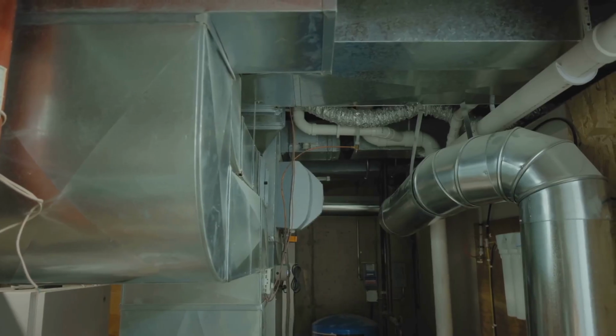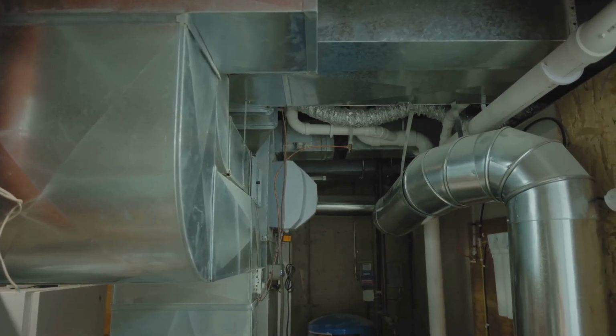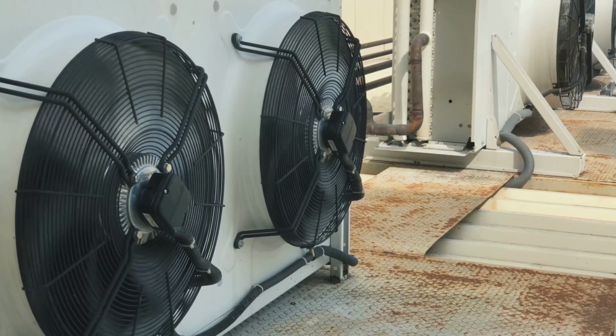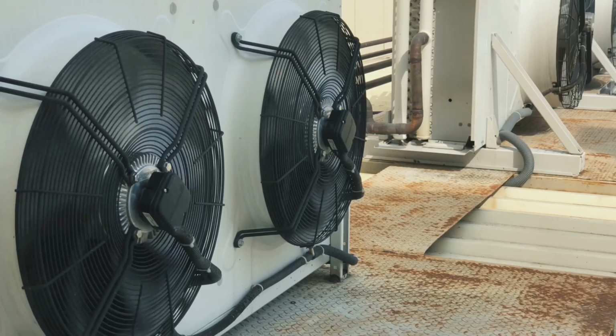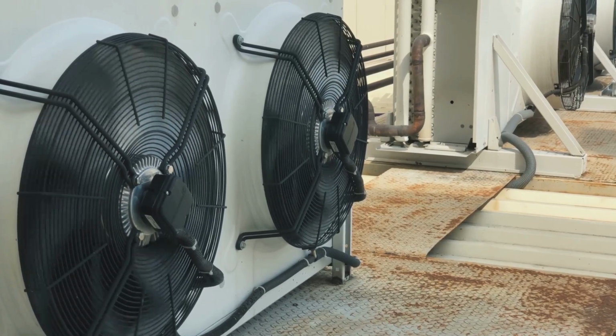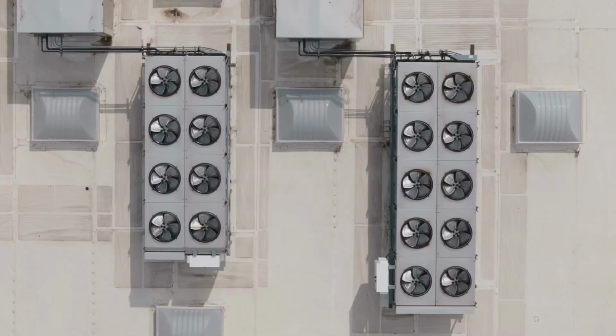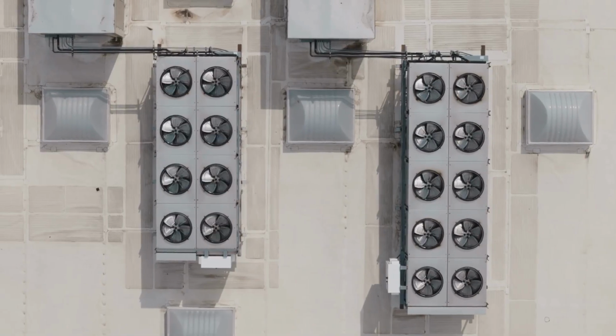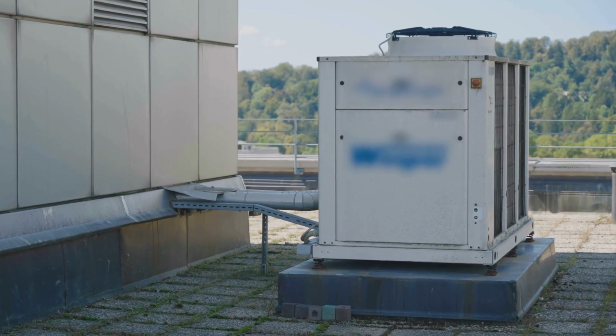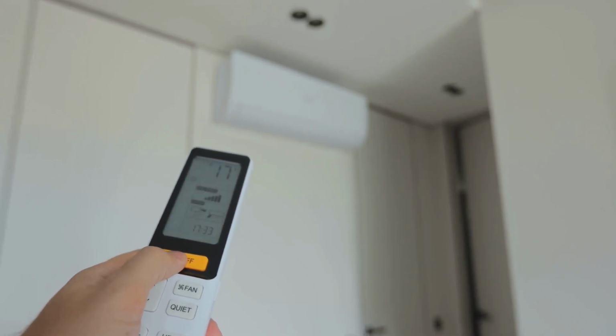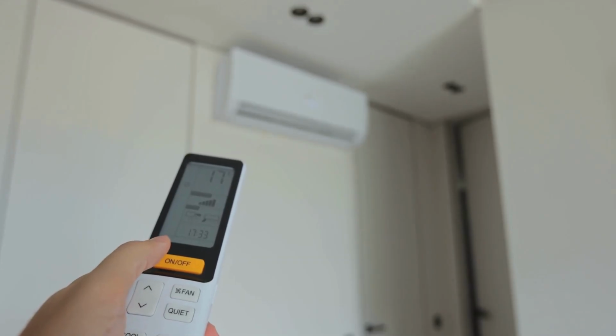2. High-efficiency MEP systems, mechanical, electrical, plumbing, the engine room. The MEP systems are the largest energy consumers in a hotel. Specifying high-efficiency equipment is critical. Heating, ventilation, and air conditioning, HVAC. Variable refrigerant flow, VRF, systems. VRF systems are a highly efficient and popular choice for modern hotels. They allow for simultaneous heating and cooling in different zones and move energy from one part of the building to another, recovering heat that would otherwise be wasted.